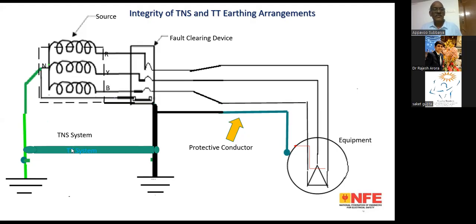So the TN-S system is more effective, I can say. Your protective device will be in a position to see the maximum fault current and trip the circuit, protecting the circuit against any earth fault as well as short circuit. Again, suppose we remove this link, I have shown one link. If we remove that link, then it becomes a TT system.